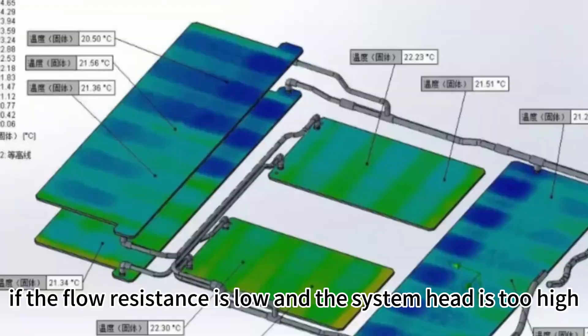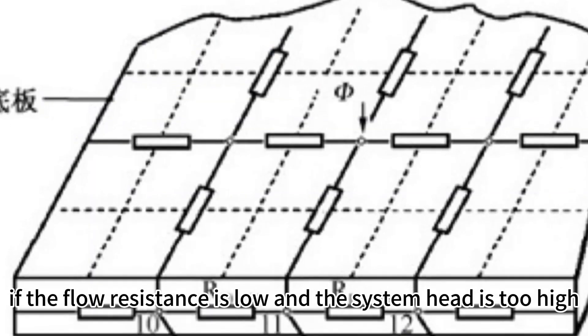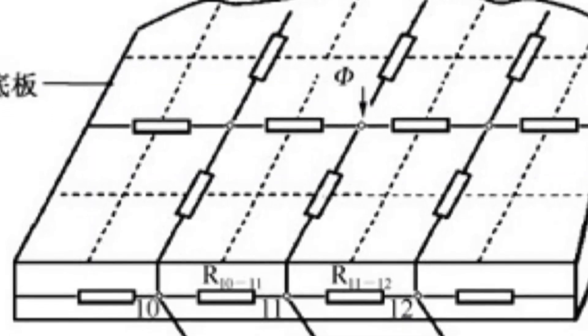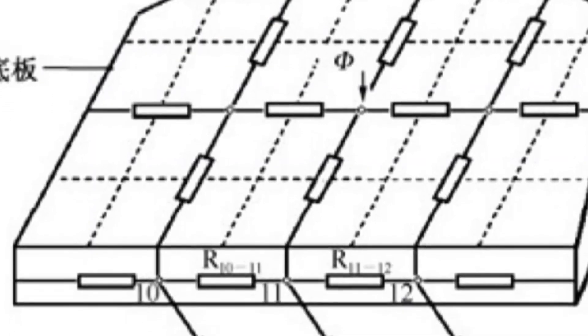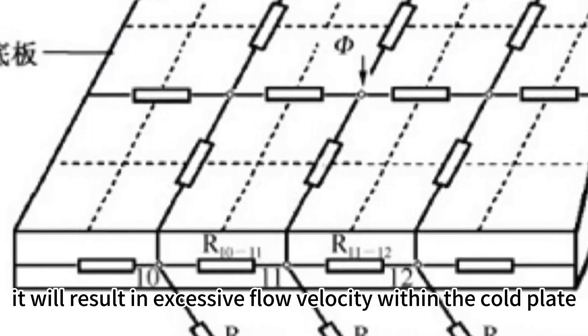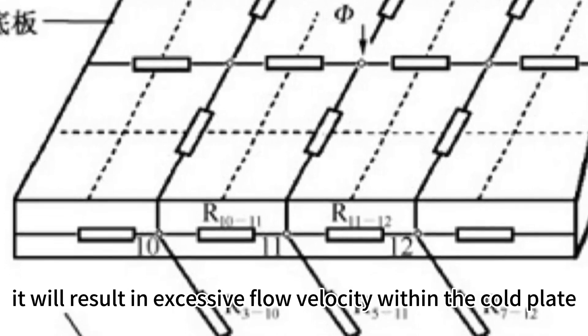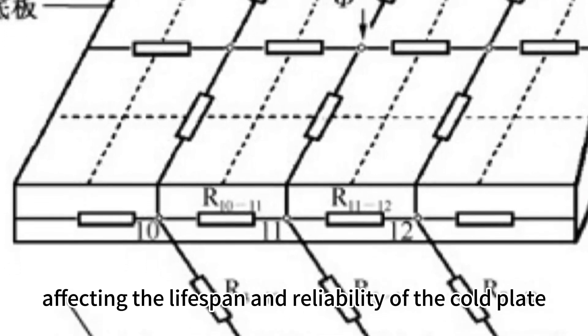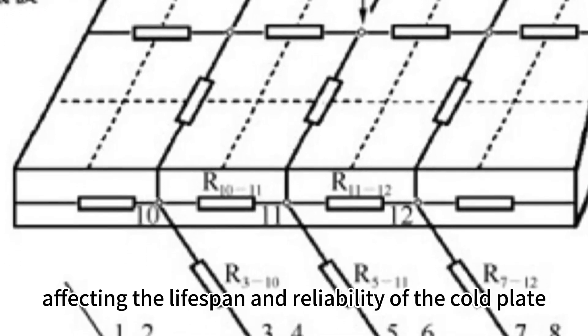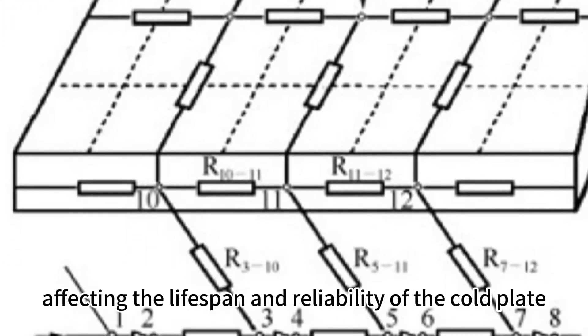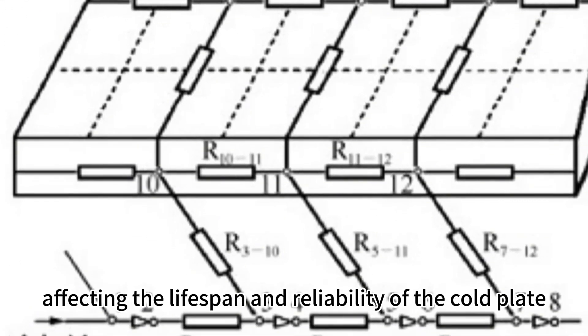Conversely, if the flow resistance is low and the system head is too high, it will result in excessive flow velocity within the cold plate, affecting the lifespan and reliability of the cold plate.